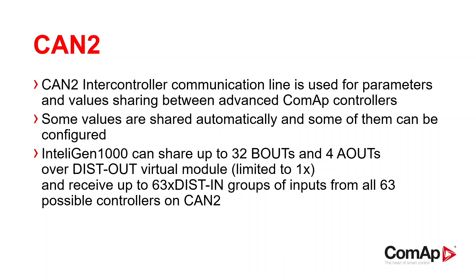The InteliGen 1000 can share up to 32 binary outputs and 4 analog outputs over the dist.out virtual module. The number of these modules is limited to 1 for each controller, and it takes the index of the controller address. Each controller can receive up to 63 dist.in groups of inputs from all other 63 possible controllers on CAN2, meaning 63 times 32 binary inputs and 63 times 4 analog inputs.